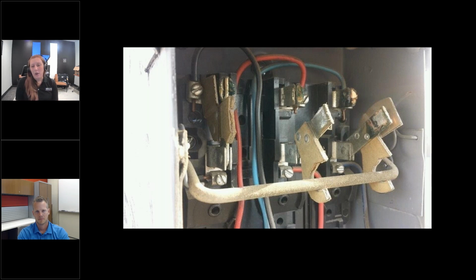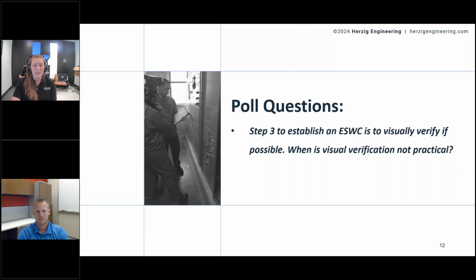Now, I've heard some people argue that if you can get eyes on the disconnect point and you see that it's disengaged, then you don't need to verify absence of voltage. And I'm like, what? I'm sorry, two things. Number 1, what if that was the wrong disconnect and it was mislabeled or whatever? You could absolutely still be exposed to hazards. And number 2, what if there's backfeeds that you're not aware of, or there's a fault in the system? No, you still have to verify it's off even if you see that the blades are open. But if you can, go ahead and visually verify. Not always possible to do that. So step 3 to establish an electrically safe work condition is to visually verify if possible.